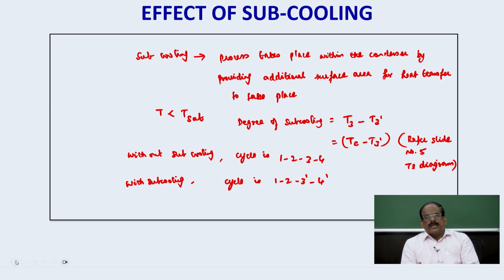It ensures that only liquid enters the expansion device. During the expansion process, there are chances of some liquid getting flashed into vapor. And of course, that vapor content also will be less when it is entering the evaporator. Maximum amount of liquid will enter the evaporator, which will be ensured by the subcooling process.